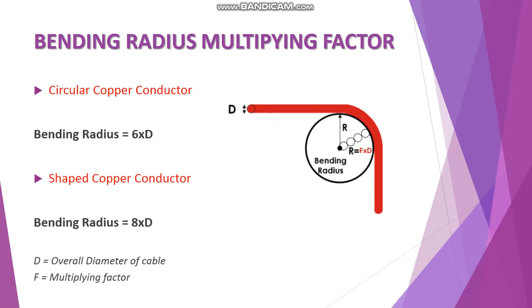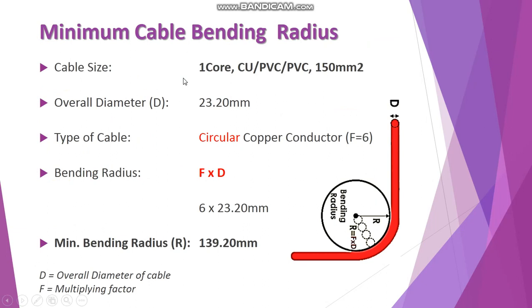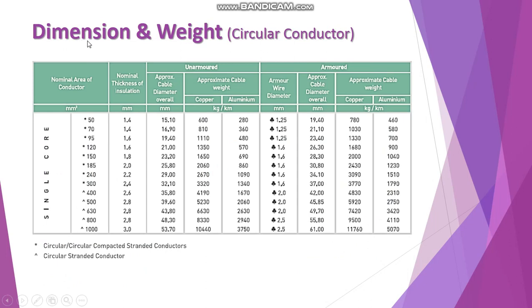Let's look at an example to make things simpler. To calculate the minimum cable bending radius, we first define which size of cable we are going to install. Here we take the example of a single-core circular copper PVC/PVC 150 mm² cable. The overall diameter of this cable is 23.20 mm — this value is derived from the dimension and weight table for circular copper conductor single-core cables. For the 150 mm² unarmoured cable, the overall approximate diameter is 23.20 mm.